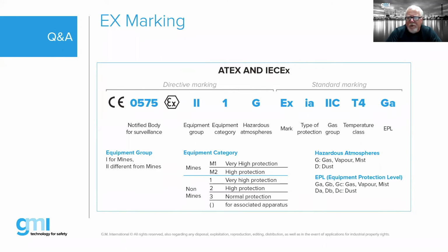So in selecting products, we have to understand a couple of things. We have to understand the zone. We have to understand the gas groups. We have to understand the temperature codes. So that standard marking, that Ia, is telling us it's good for zone 0, zone 1, and zone 2. The Roman numeral II C is telling us it's good for all gas groups. And T4 means that product can be used in any gases that are rated at T4, T3, T2, or T1. If we have a gas that's rated T5, that means that gas has an auto-ignition temperature of somewhere above 100 degrees C, and you could not use that product in an environment in which T5 was the requirement for the project, if that makes sense.